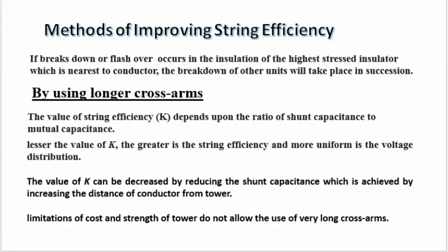Now, how can we improve the efficiency of string? If breakdown or flashover occurs in the insulator of highest stress, which is nearest to the conductor, then after that breakdown, the other units will also undergo the breakdown phenomena. We have to improve the string efficiency, and the common method which is used to improve the string efficiency is by using long cross arms.